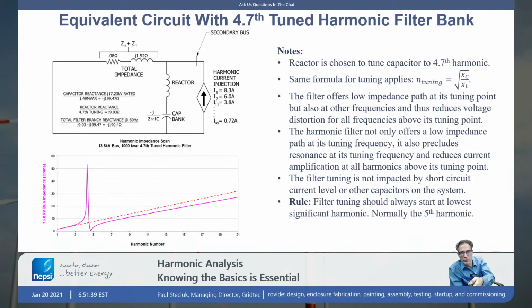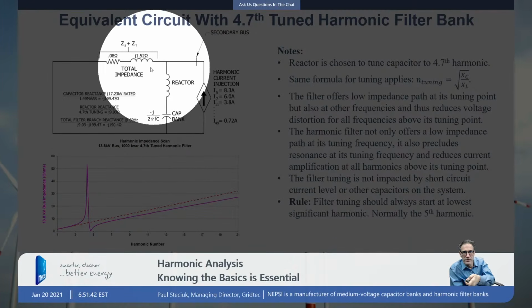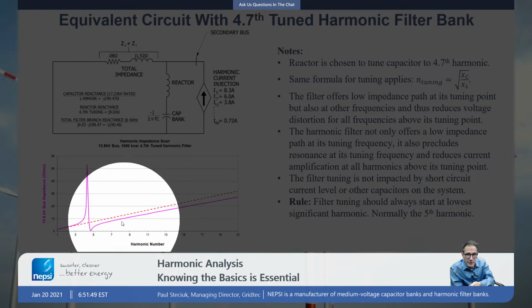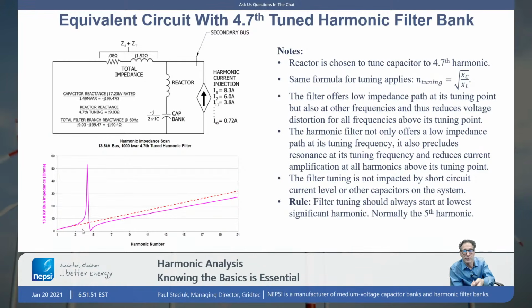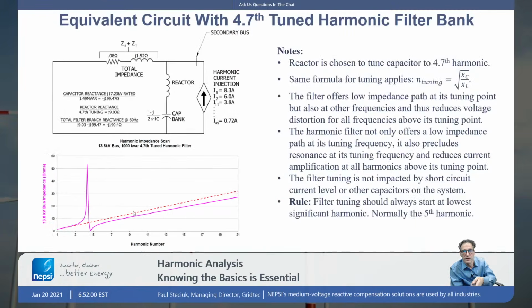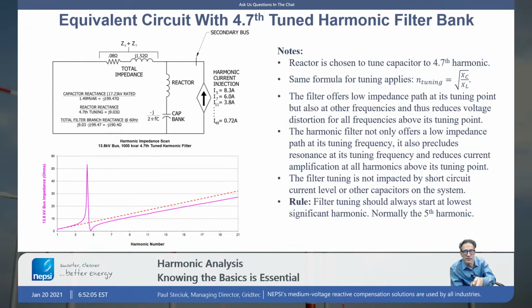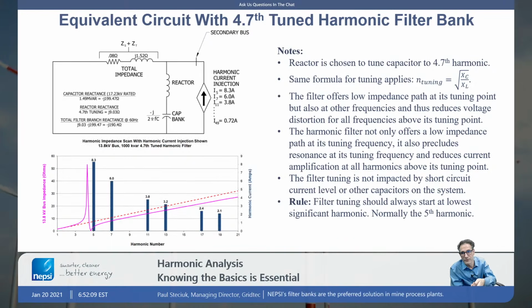So look at the impedance curve here. We recreated the impedance curve here with this magenta line. We're looking into the network. The red dashed line is that reference line that we started with in this presentation, which is the transformer source impedance line. And we overlaid on top of that the impedance curve of the network with the filter.